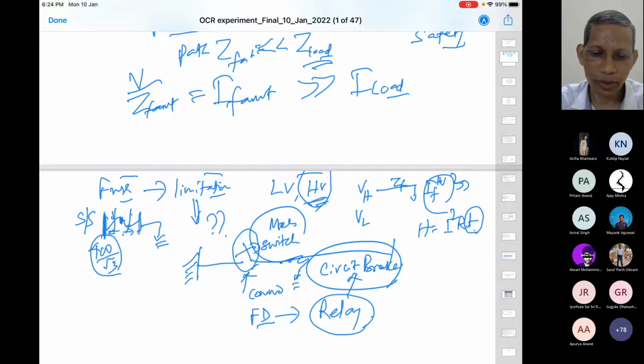There are different types of circuit breakers: air circuit breaker, SF6 circuit breaker, where SF6 is an insulation medium widely used in high voltage, vacuum circuit breaker, where vacuum itself is an insulation, and oil circuit breakers. These are the typical circuit breakers used in the power system. The insulating medium, whether SF6, oil or air, is there to intervene in the faulted part of the system as quickly as possible. A high voltage system requires operation in the millisecond order. We will see during our experiments how it is done.